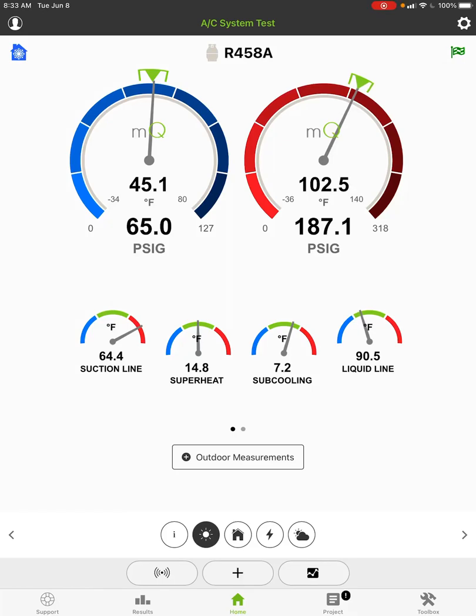Hey, Jim Bergman with MeasureQuick. Once in a while we get a question on superheat and subcooling calculations and why they don't appear to agree. I'm on a blended refrigerant here, R458A, and you'll see that it looks like I have a saturation temperature of 45 degrees and a suction line of about 65 degrees. Keep the math simple and it looks like a superheat of about 20.